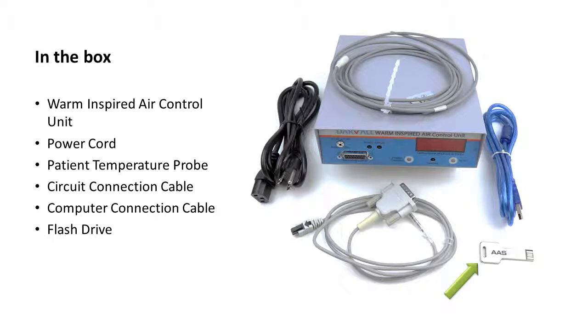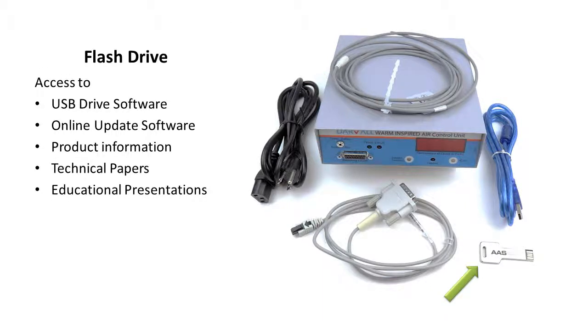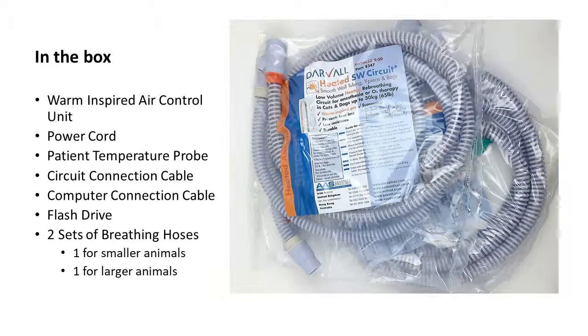You'll also find a key-shaped USB flash drive. This flash drive contains access to the USB drive software, the online update software, product information, technical papers, and educational presentations. You can update the software of the control unit online with the computer connection cable using the USB drive software you downloaded onto your computer and the software update found online. And you'll find two sets of smooth wall breathing circuits, one for smaller animals up to 60 pounds and one for larger animals over 60 pounds.